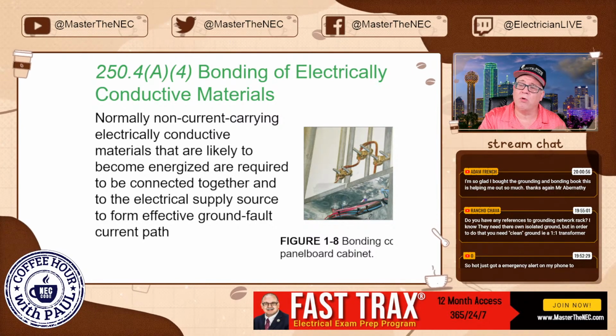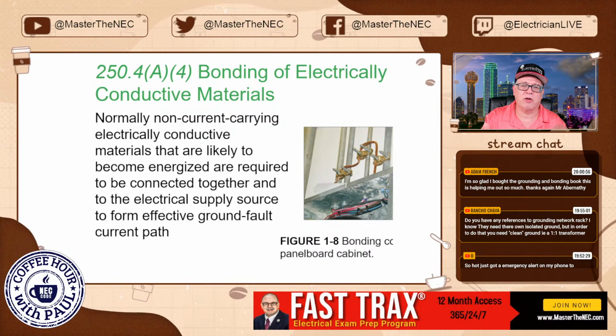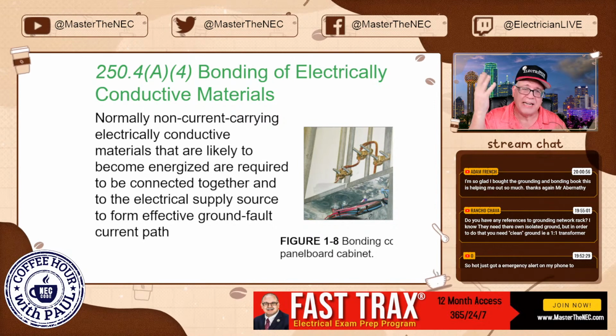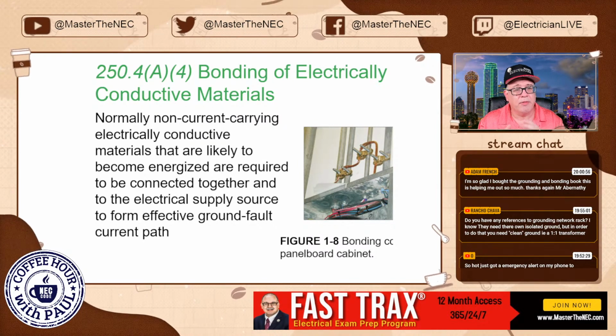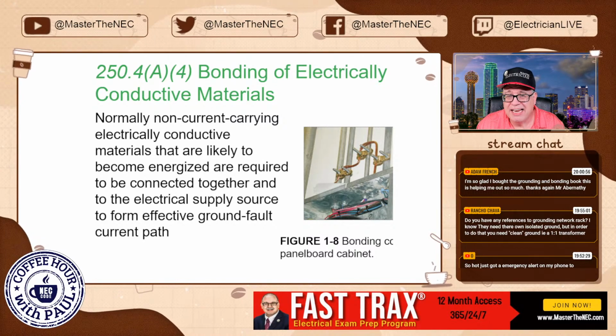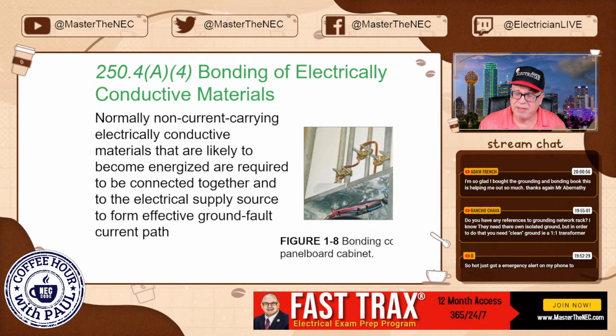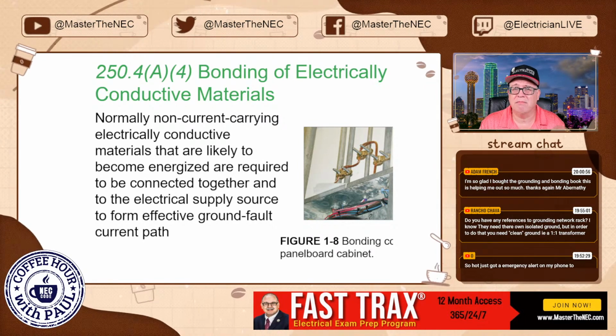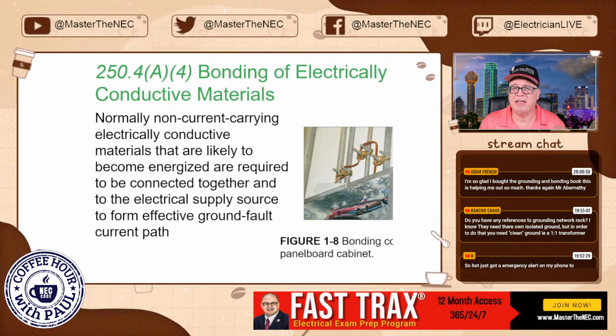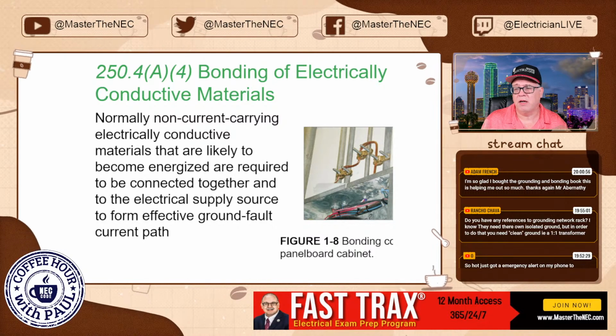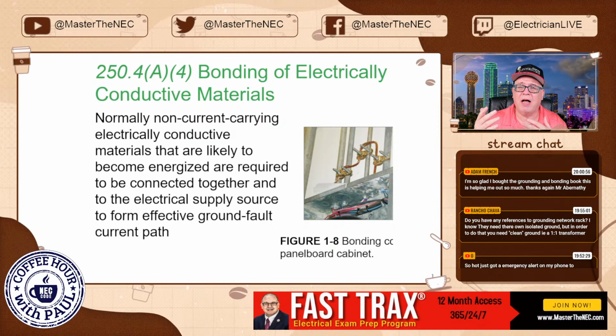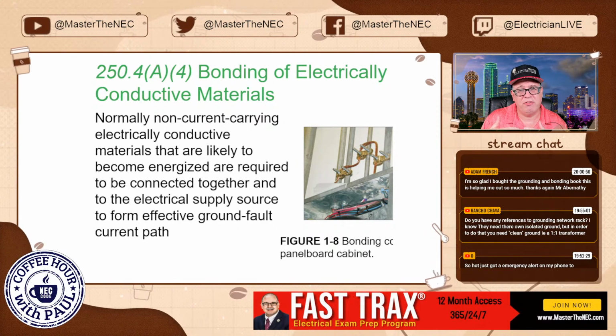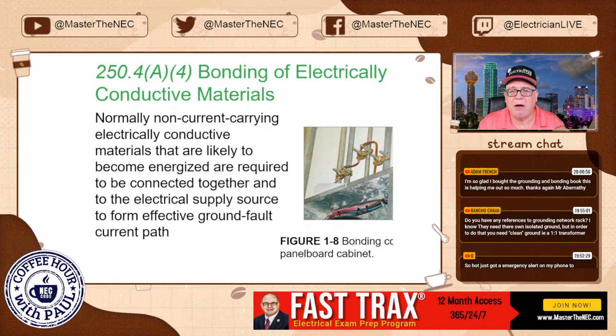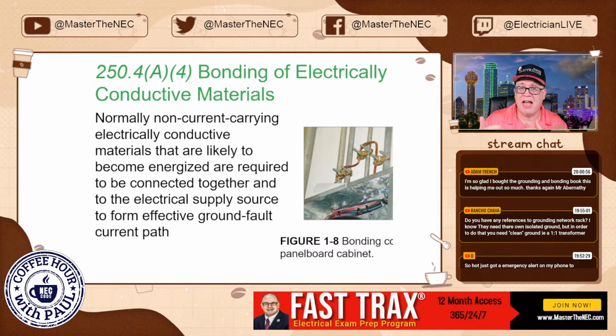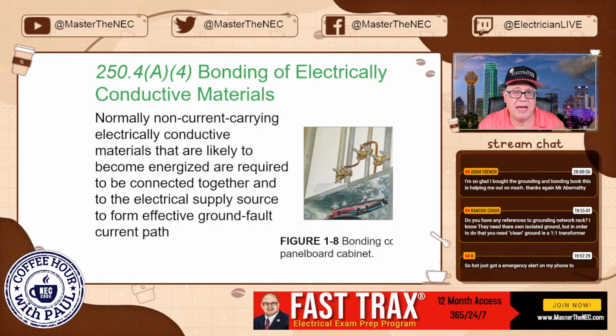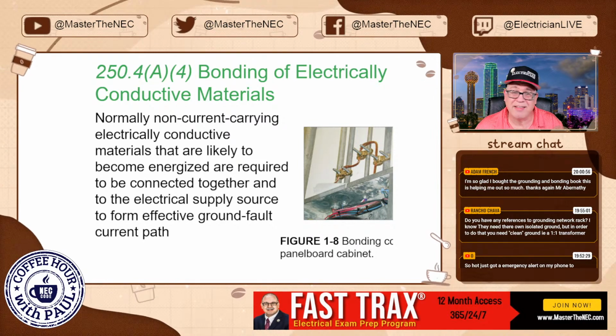But this is where people reach beyond this, and sometimes inspectors will say, well, that's likely to become energized, I'm going to need you to bond it, okay? The issue you've got to identify is, is it really likely to become energized? And you're going to have to work with the AHJ on that. I can tell you right now, I've had people contact me because MC cable is within a couple inches of a metal frame, and they want the darn thing bonded because they say that the MC could become energized and then touch that metal. So it's likely. I would say that is highly unlikely if it's not touching now and you've secured and supported your MC cable in accordance with 330.30. But that's just the things you've got to deal with, okay?